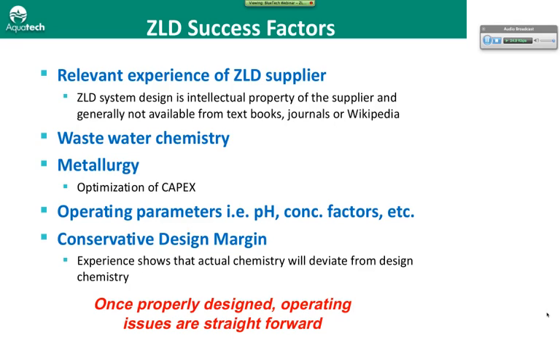It's important to understand the operating parameters of the system: pH, concentration factors, and whether the wastewater tends to foam, and to include a conservative design margin. One challenge we face as ZLD system suppliers is that our equipment has to perform over a large variability in chemistry. It's not like a boiler, where there's normally a tight window on water chemistry requirements that everyone understands. The ZLD system sits at the end of the pipe, and everything in the plant that washes into the drains eventually ends up at the ZLD plant. So we need to be very conservative in the design.